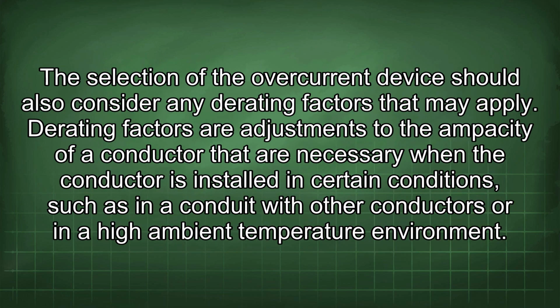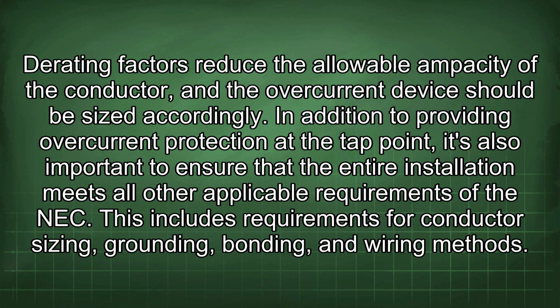The selection of the overcurrent device should also consider any derating factors that may apply. Derating factors are adjustments to the ampacity of a conductor that are necessary when the conductor is installed in certain conditions, such as in a conduit with other conductors or in a high ambient temperature environment. Derating factors reduce the allowable ampacity of the conductor, and the overcurrent device should be sized accordingly.